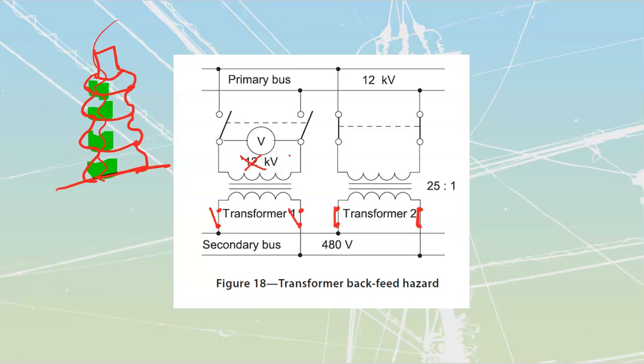Watch out. Be very, very careful with transformer backfeeds, and be very careful with what you allow a customer to backfeed as well. This is a huge concern to BC Hydro. If BC Hydro finds out that you are backfeeding onto your panel, this is why we've got transfer switches that disconnect us from Hydro when we operate a generator. There's this huge danger where people make a double-ended extension cord where they stick two male ends on an extension cord. Then they plug one into the generator and one back into their house, and they'll backfeed their house, as they call it. What's actually happening is, unless they've thrown the main breaker, they're going to be backfeeding the neighborhood transformer as well.